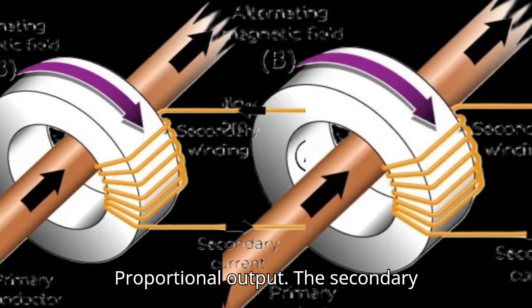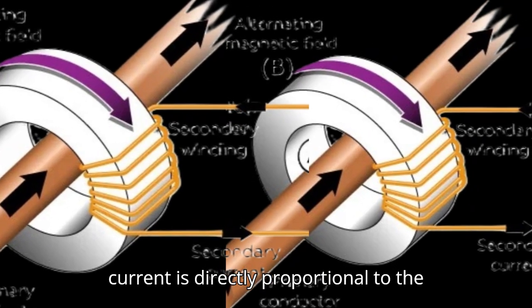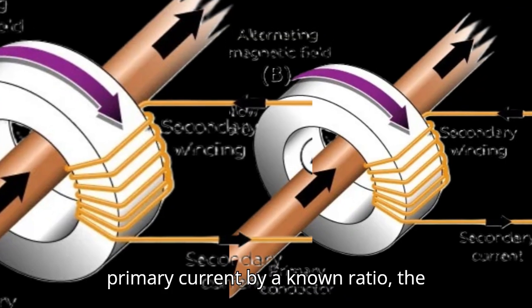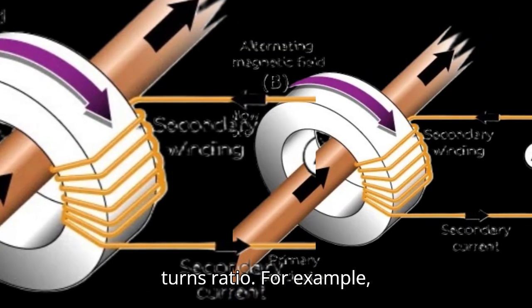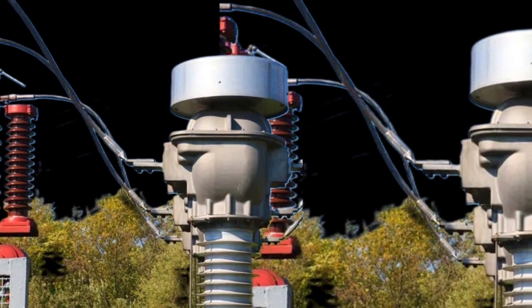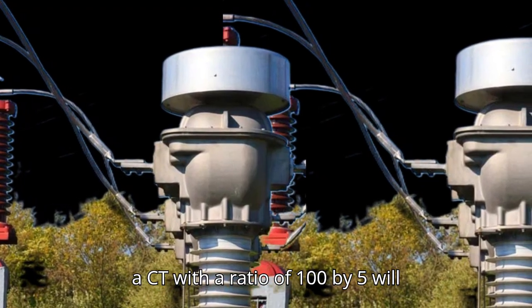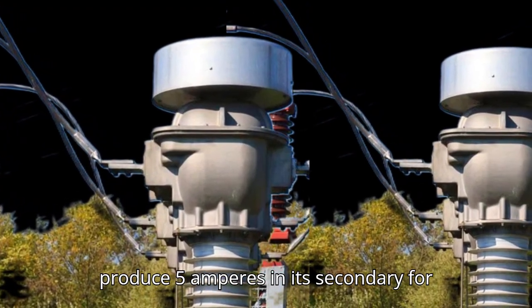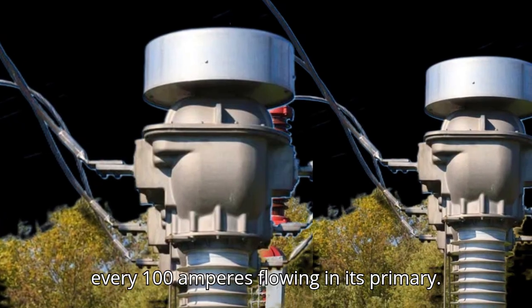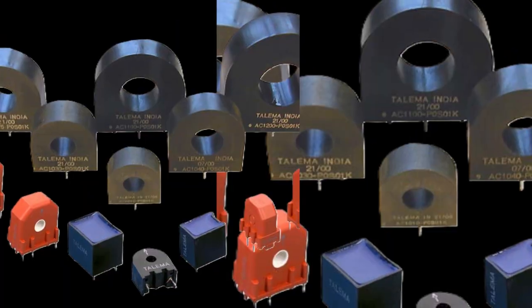The secondary current is directly proportional to the primary current by a known ratio, the turns ratio. For example, a CT with a ratio of 100/5 will produce 5 amperes in its secondary for every 100 amperes flowing in its primary.